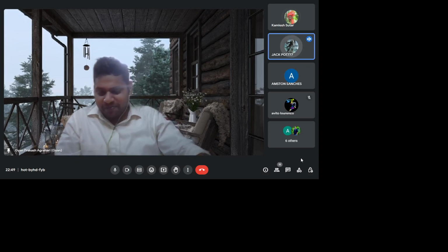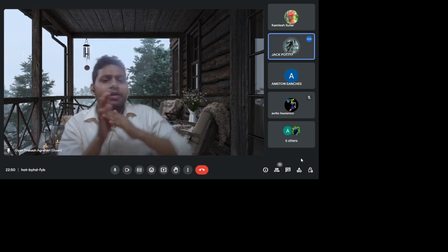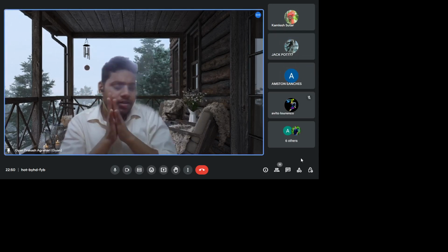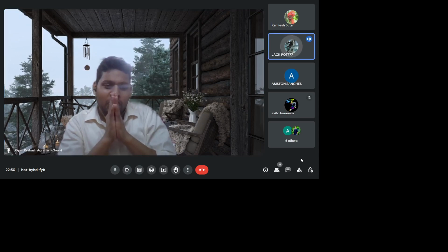You know about the relation between temperature and pressure? When pressure increases, temperature increases. What if the boiler is shut down? Temperature decreases, right? Then pressure will drop. The steam will condense into water. Steam volume is higher than water volume, so it will condense to try to reduce the volume. That creates a void space or vacuum that causes the implosion.